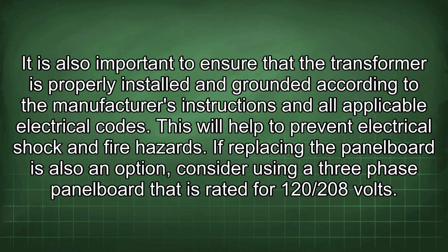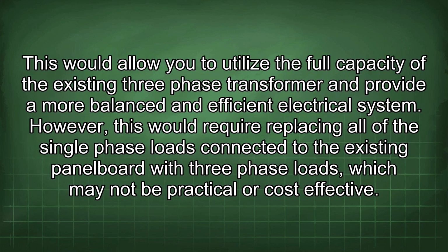If replacing the panel board is also an option, consider using a 3-phase panel board that is rated for 120/208 volts. This would allow you to utilize the full capacity of the existing 3-phase transformer and provide a more balanced and efficient electrical system. However, this would require replacing all of the single-phase loads connected to the existing panel board with 3-phase loads, which may not be practical or cost-effective.